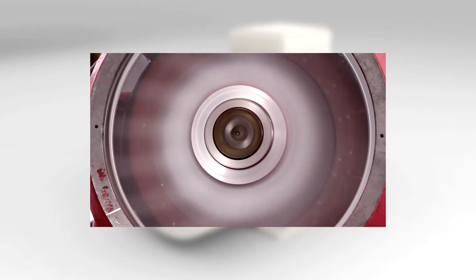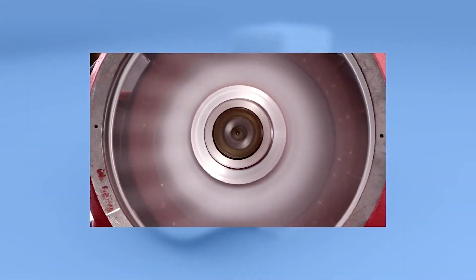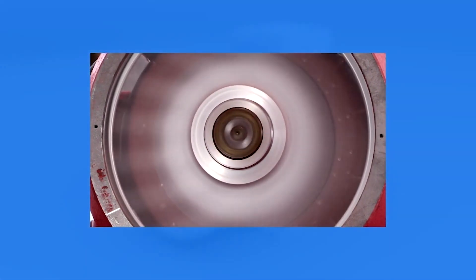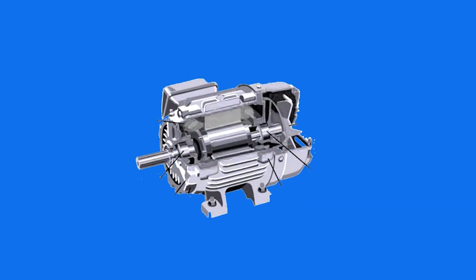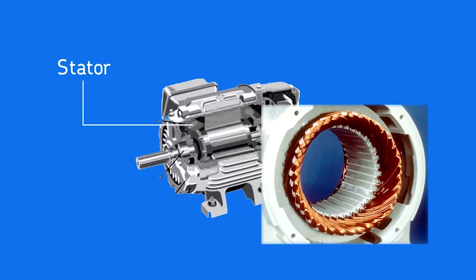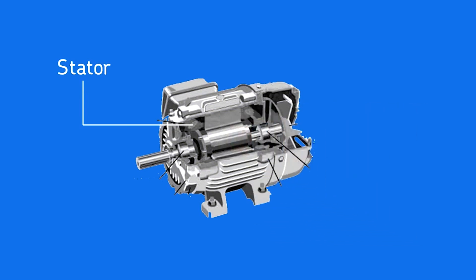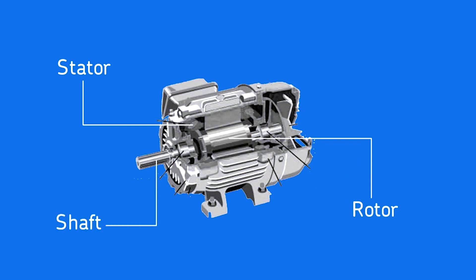Industrial AC induction motors use magnetic fields to cause shaft rotation. Magnetic fields are created by electric currents. The AC power source provides the currents that flow in the motor. The stationary part of the motor — the stator — is made of several wire loops which are physically aligned to create strong magnetic fields. Due to the AC nature of the power source, the magnetic field direction rotates in the center of the stator, where the rotor is located.